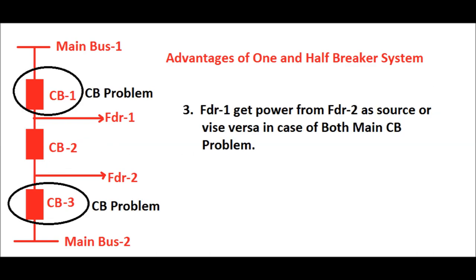Now consider a case where there is a circuit breaker problem in CB1 and at the same time CB3 is under maintenance, or vice versa — that is, a CB problem in both main bus side circuit breakers simultaneously. Even in that case, feeder 1 can still get power, sourced through feeder 2 via the tie circuit breaker CB2 in closed position.